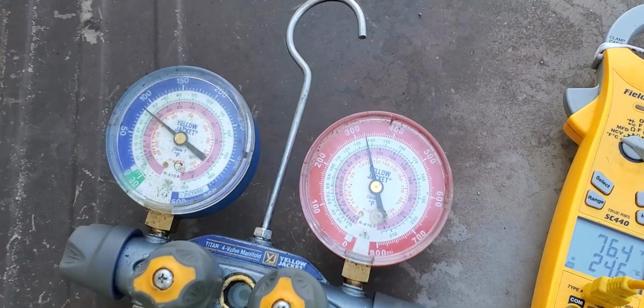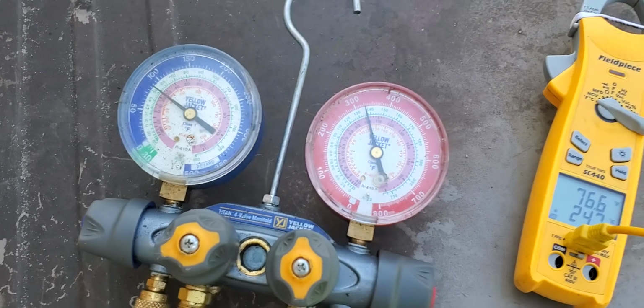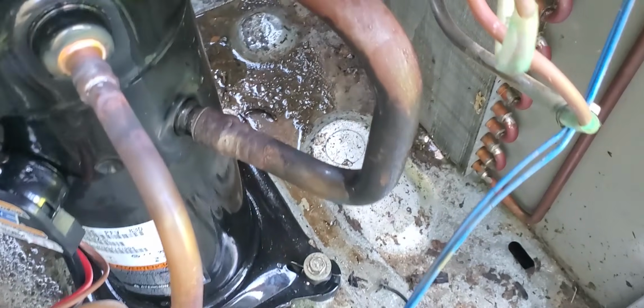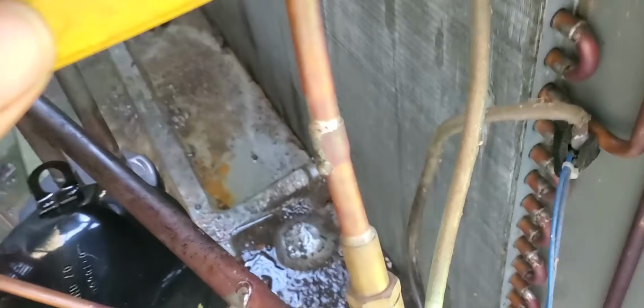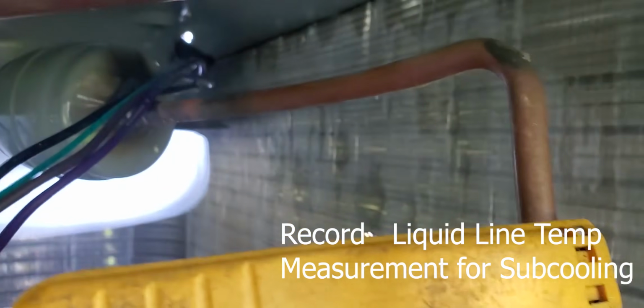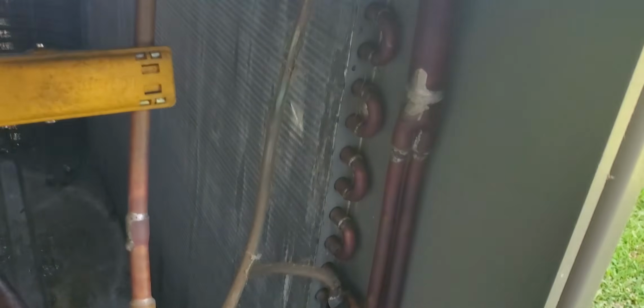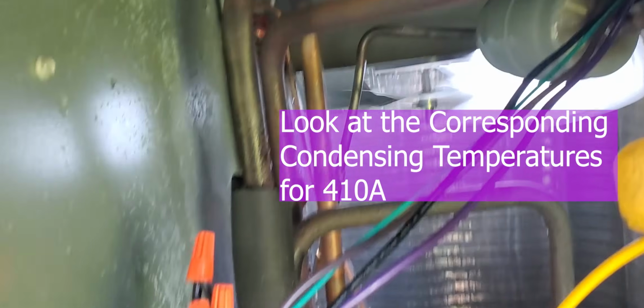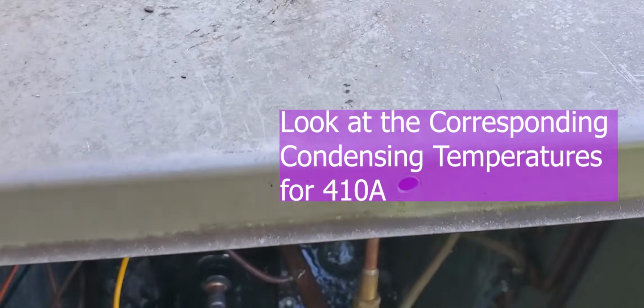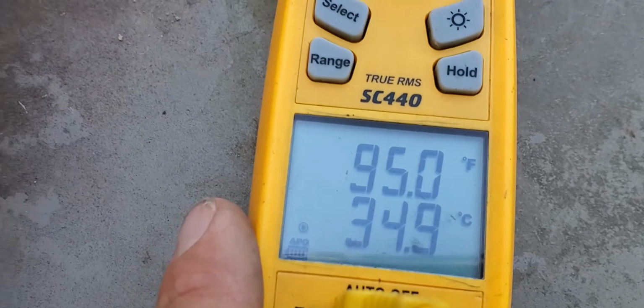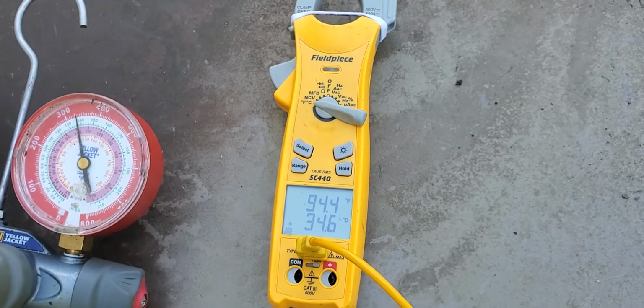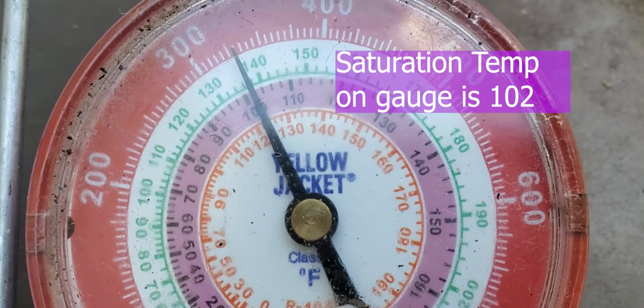Let's talk about checking refrigerant charge by subcooling, start to finish. We turn on the refrigeration system. We let it run 10 to 15 minutes. We ensure there is proper airflow through the condenser and evaporator coils. We take a high side pressure measurement, which gives us the PSI of the high side. We use that head pressure measurement to determine the temperature of the refrigerant in the condenser. There are two ways of doing this. Some high pressure gauges have displays showing saturated refrigerant temperatures. You see this? This is the saturated refrigerant temperature that corresponds with the pressure measurement. If your gauge does not have this, check a pressure temperature chart. That shows the corresponding values for the refrigerant in the system.